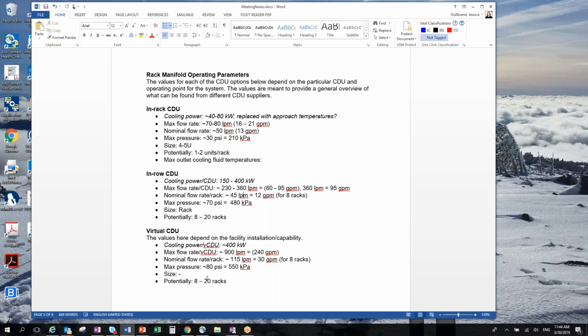Okay, in that case I have two questions. One, does that mean the propylene glycol solution would have to be used to exhaust the heat to the environment eventually? And the other, would the pressure rating then be dependent on the number of stories the data center has? Like if it's a multi-story data center, all the equipment would have to be rated for a much higher pressure value? Yes, someone please correct me if I'm wrong, but that seems to be my understanding from reading stuff online.